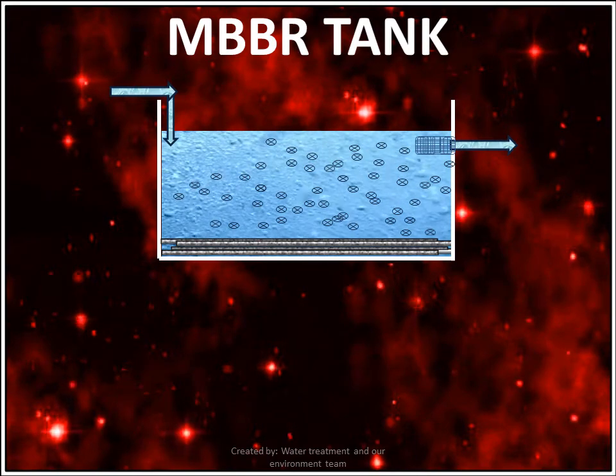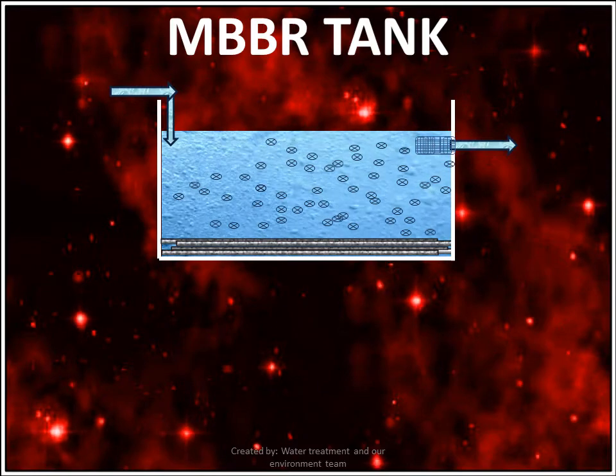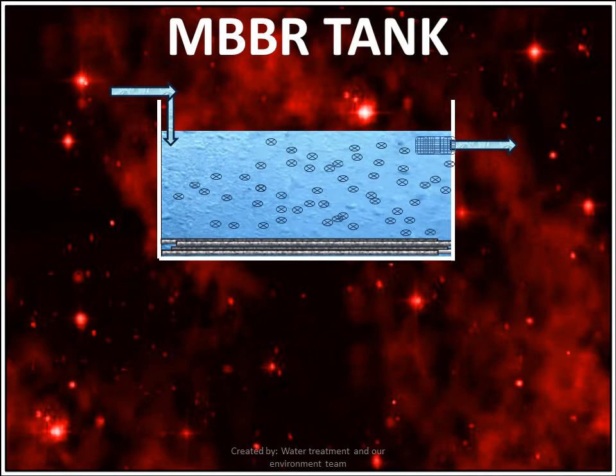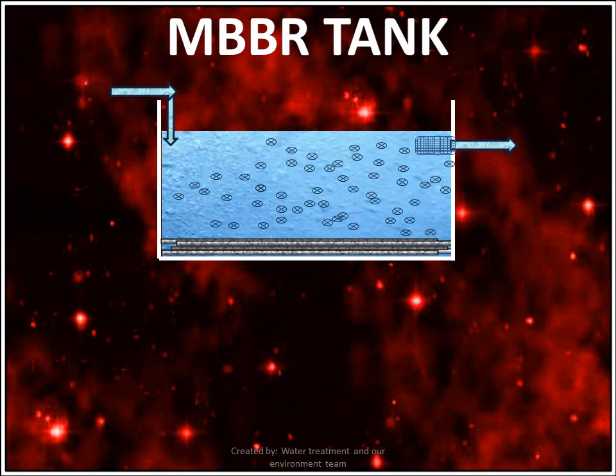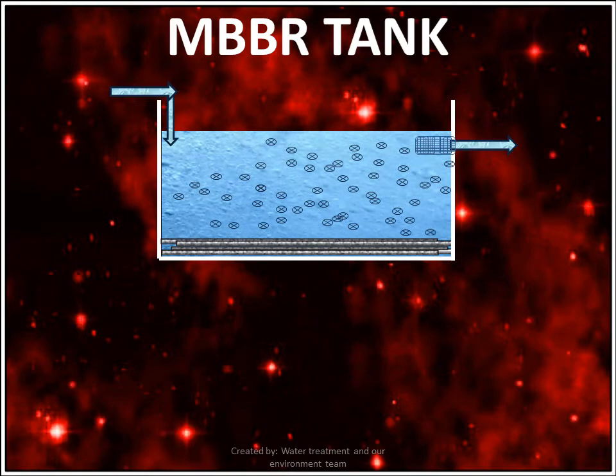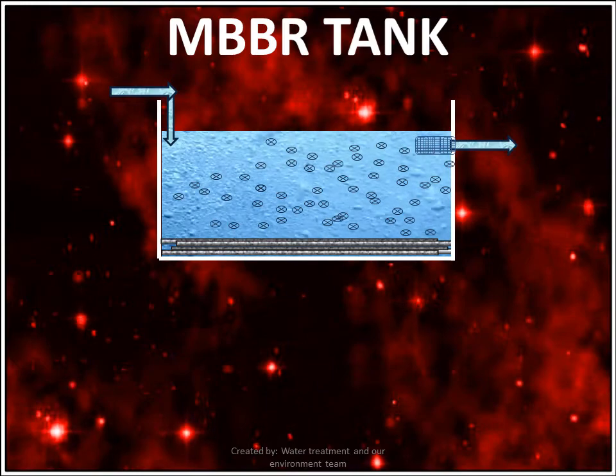The MBBR process provides an advantage for plant upgrading by reducing the solid loading on existing clarifiers. However, the presence of packing material discourages the use of more efficient fine bubble aerator equipment, which would require periodic drainage of the aeration zone and removal of packing for diffuser cleaning.